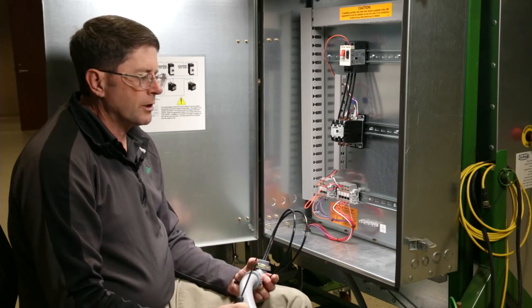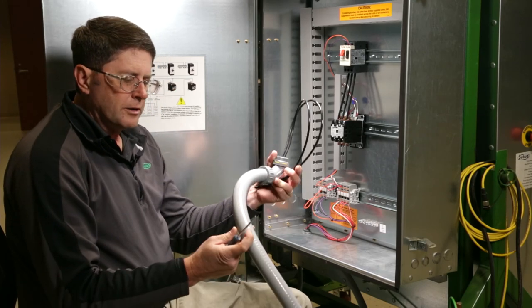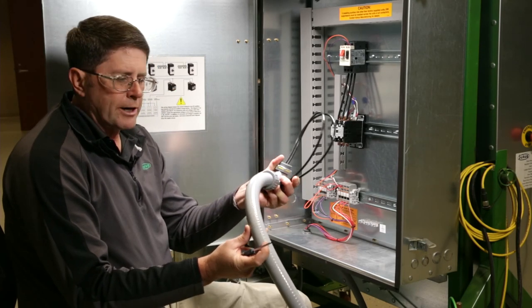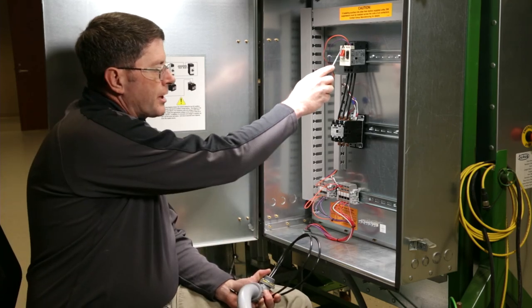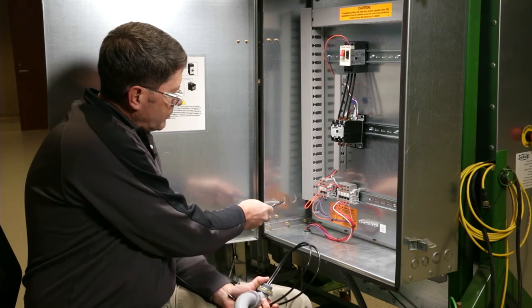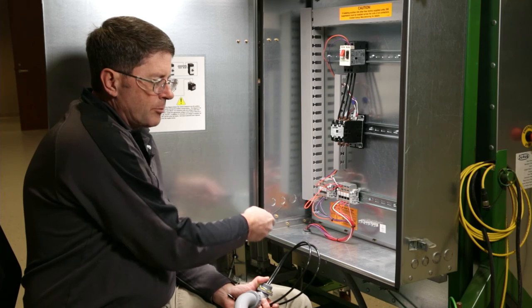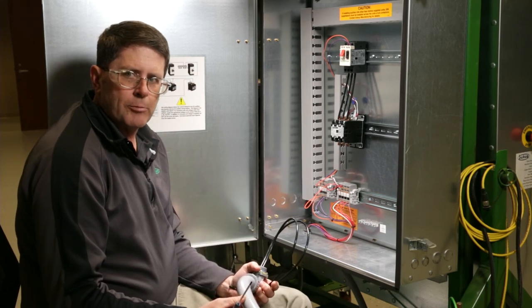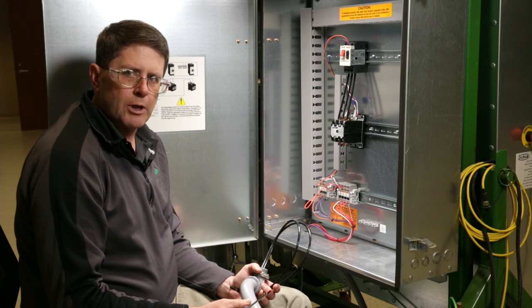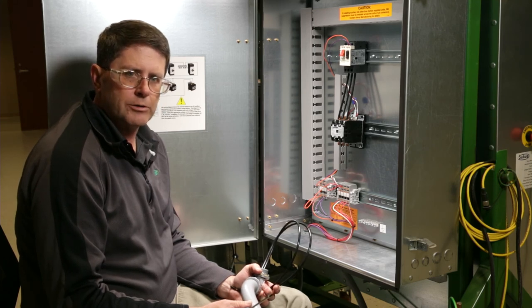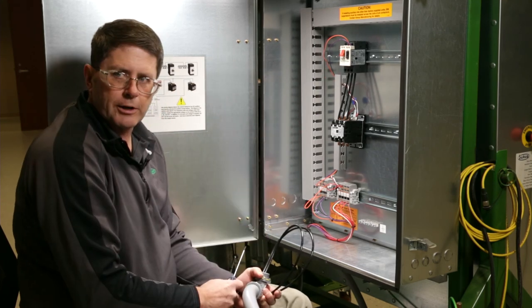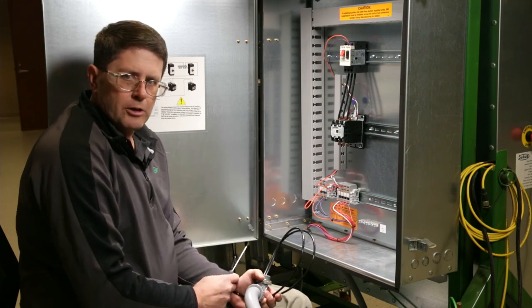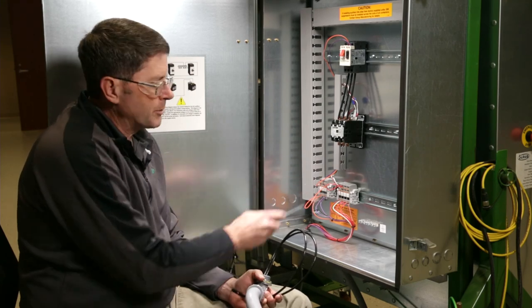To complete your auxiliary circuit installation, the kit will be supplied with conduit and wire to go to the top of your starter protector. And then you'll need to use a knockout in the side of the box. And then this will need to be taken into the main power box and hooked to the distribution block to provide that main power to the top of your starter protector. And then you'll need to hook up your motor leads from the magnetic starter.